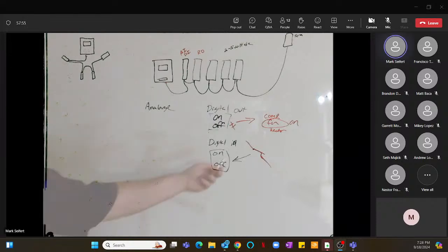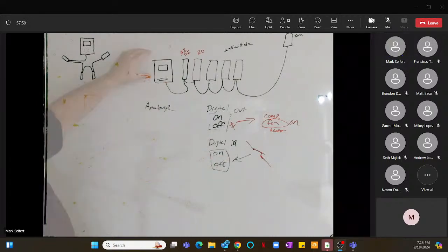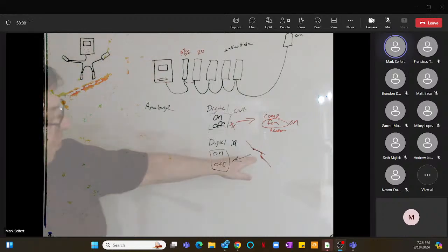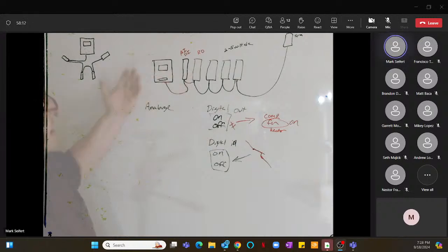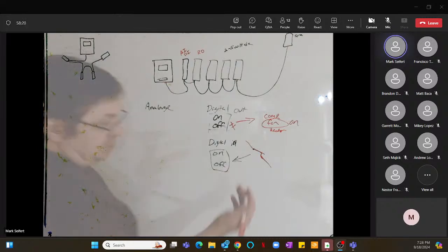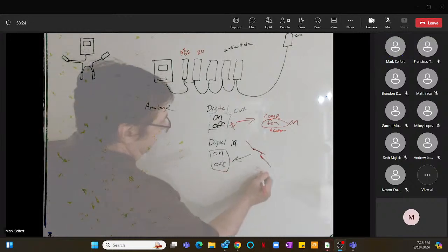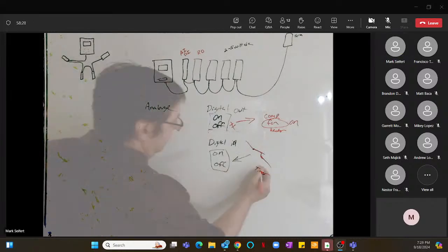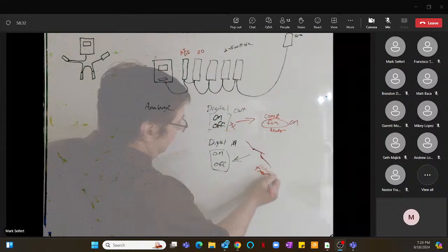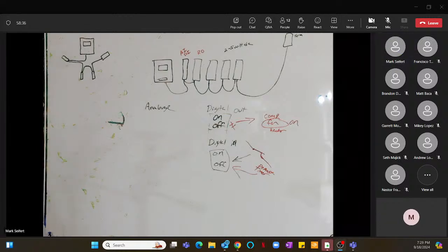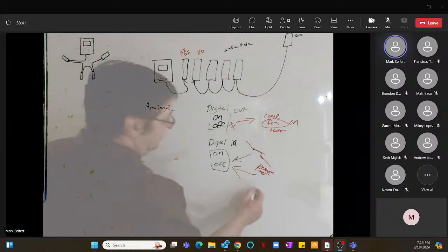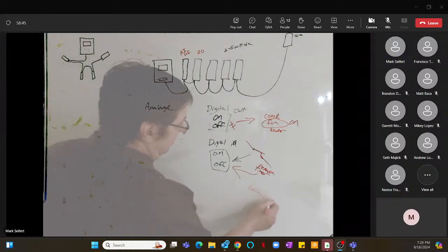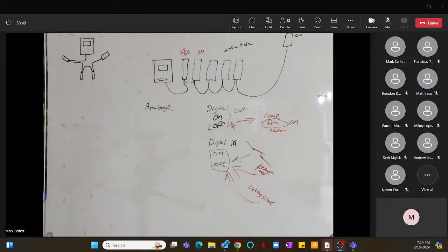Now, obviously it's not just the door switch that turns that fan on and off, and that's where the programming comes in. In the program you'll tell it, also in defrost, shut the fan off. So the door switch can shut the fan off here, and defrost. It needs no other inputs other than a time. So a digital input could also be a timer, or defrost time. That's also a digital input. A lighting schedule, it's a digital input. What other kind of digital inputs are there? Termination.